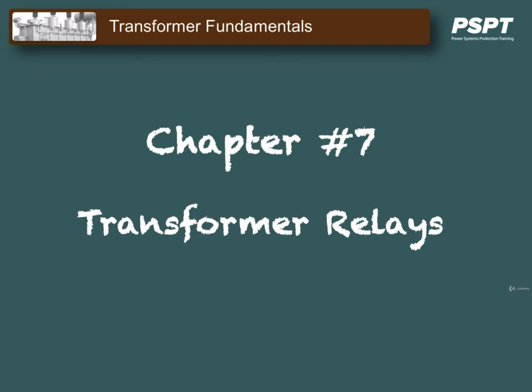However, we are also going to show you some relatively new transformer relays that are called IEDs, or Intelligent Electronic Devices, that are basically computers that work extremely fast and provide multiple functions for protecting the transformers. We're also going to look at the oil flow protection, the Buchholz relay, towards the end of this chapter, which is used in most of the oil-immersed transformers that are protected in today's protection schemes.